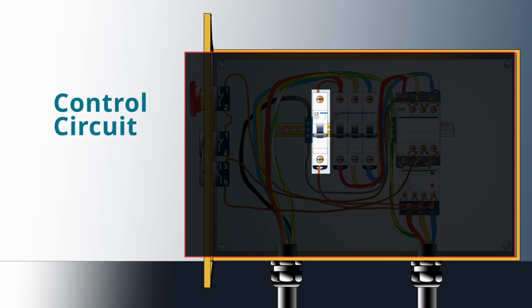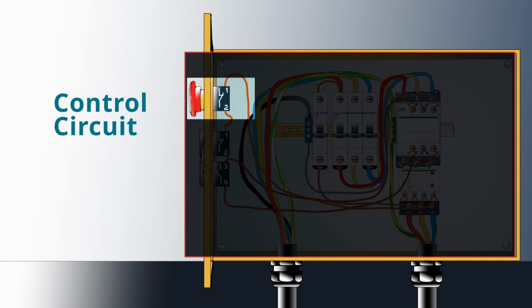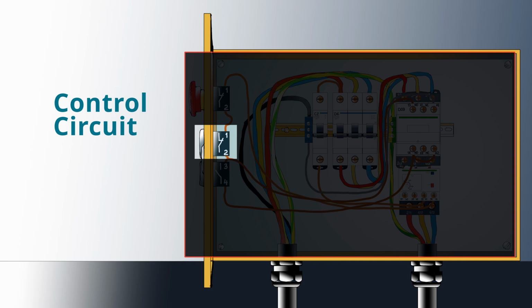On the other hand, the control circuit consists of the control circuit breaker or fuse, normally closed contacts on the overload relay, generally labeled 95 and 96, the emergency stop or e-stop button, the stop push button, the start push button, and normally open contacts on the contactor, usually labeled 13 and 14, which we call auxiliary contacts or auxiliary hold-in contacts. The contactor coil, generally labeled A1 and A2, and the neutral terminal, depending on our choice of control voltage.